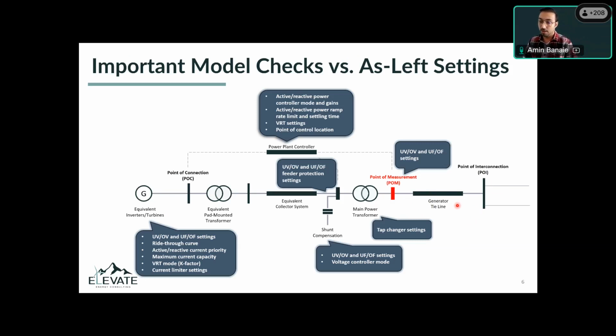So it's important to maintain that power flow solution that you got for solving 0.95 at POI. In most cases, that's not going to impact the result since this impedance is not that large, but we've seen cases where this impedance for the tie line has had very large charging current. So you want to make sure to capture that P, Q, and V that you got from the solution for 0.95 at POI.